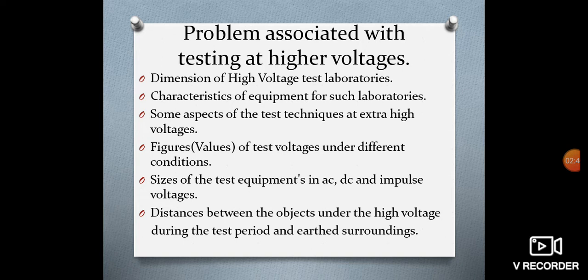Characteristics of equipments for such laboratories. Even the equipments which are installed in the high voltage laboratories are not of general type, but they are characteristic equipments and specific to the high voltage laboratories. Some aspects of the test techniques at extra high voltages. Even the test techniques or the procedure followed during high voltage testing is very important and specific to high voltage laboratories, and the values of test voltages under different conditions are different, and the values we take for the test voltages are very typical and of huge magnitude.